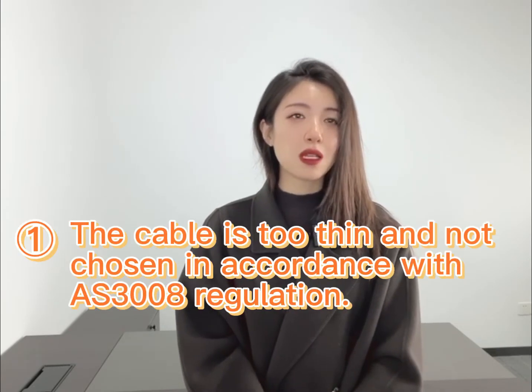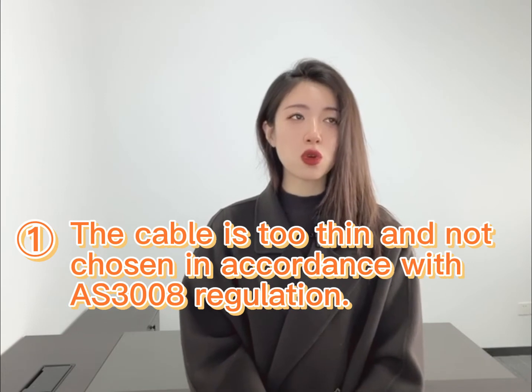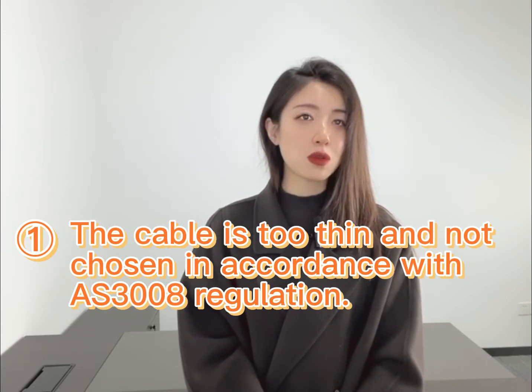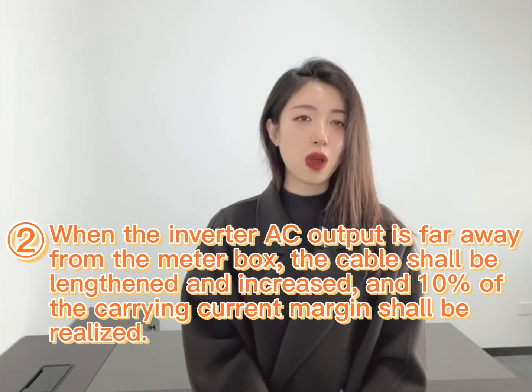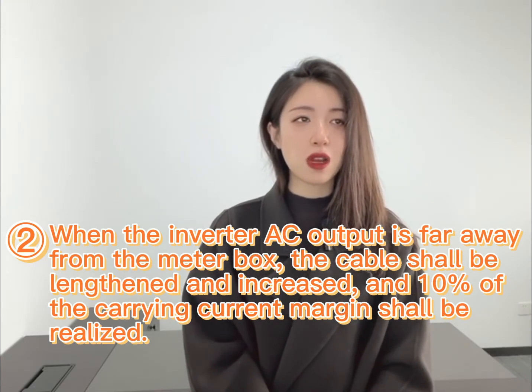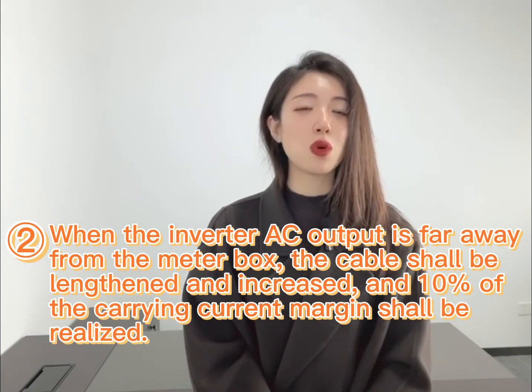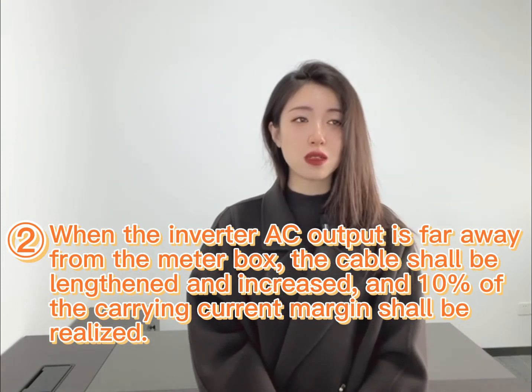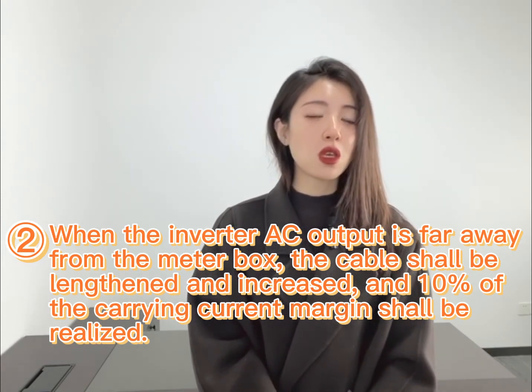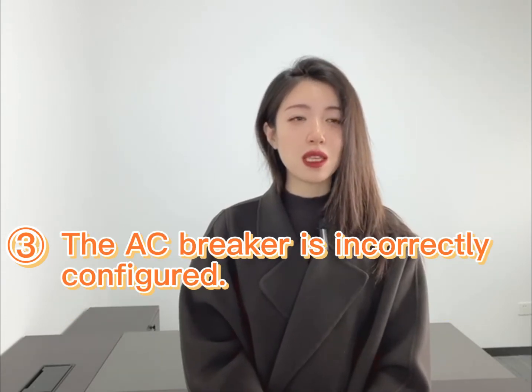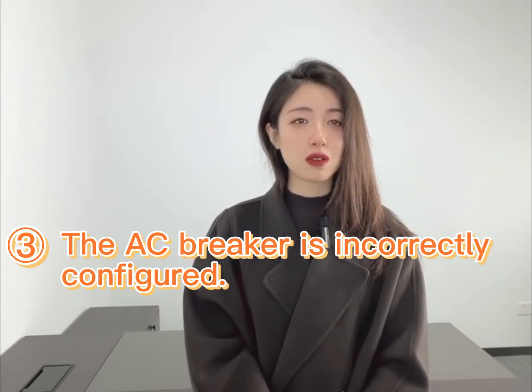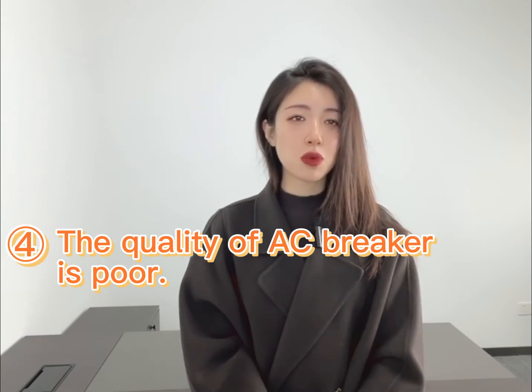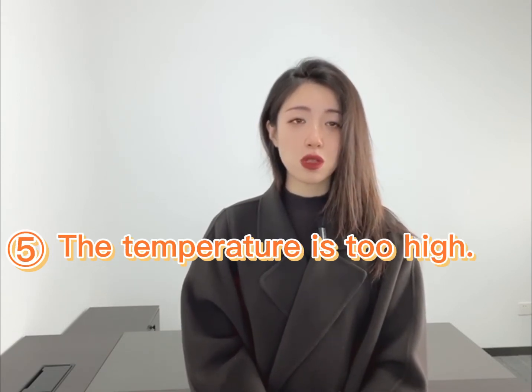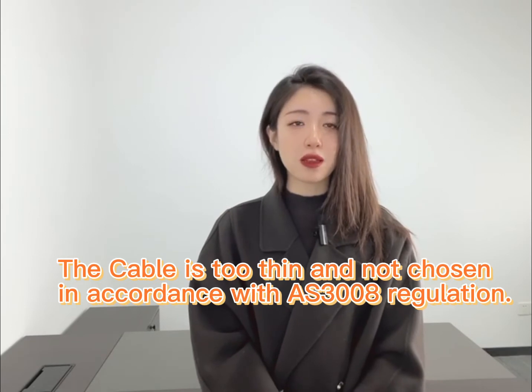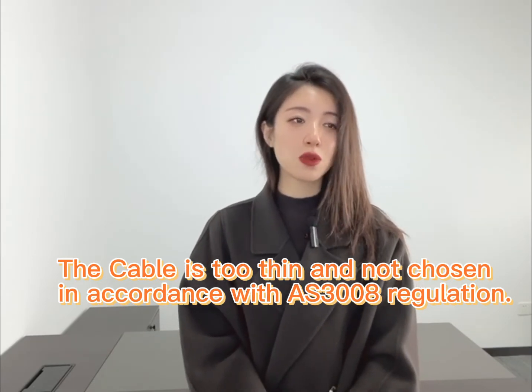What are the main causes of AC breaker tripping off? 1. The cable is too thin and not chosen in accordance with the AS3008 regulation. 2. When the inverter AC output is far away from the meter box, the cable shall be lengthened and increased, and a 10% carrying current margin shall be provided. 3. The AC breaker is incorrectly configured. 4. The quality of the AC breaker is poor. 5. The temperature is too high. The cable is too thin and not chosen in accordance with the AS3008 regulation.